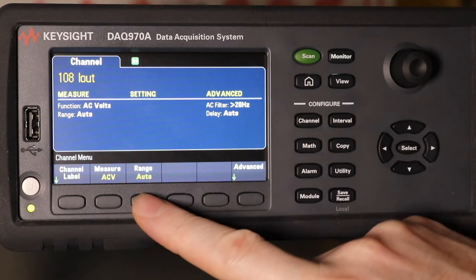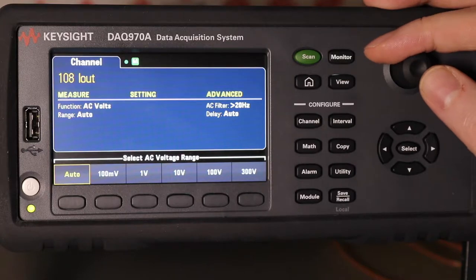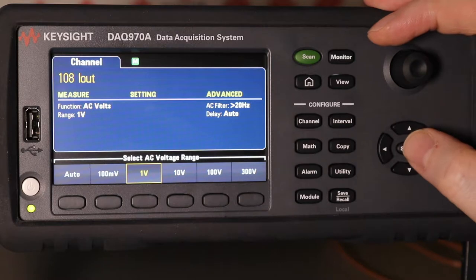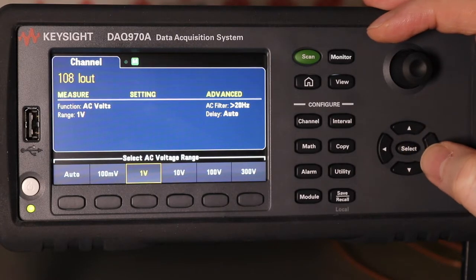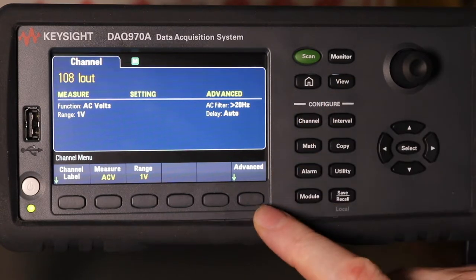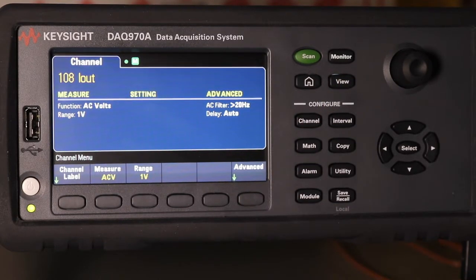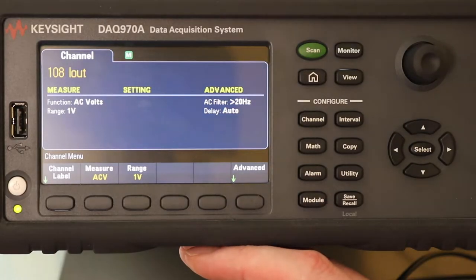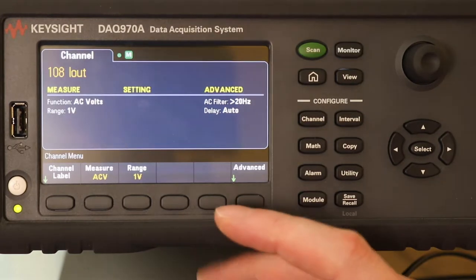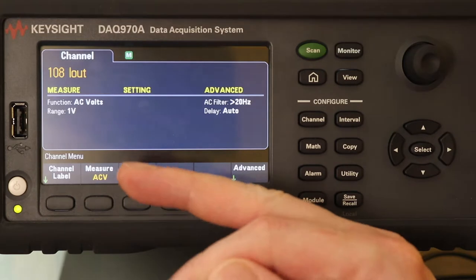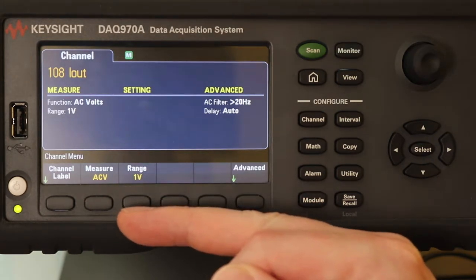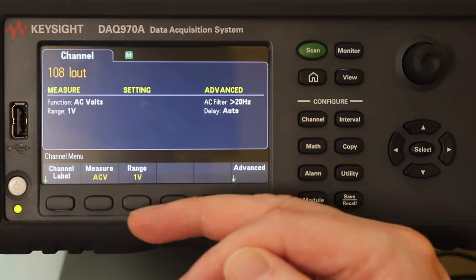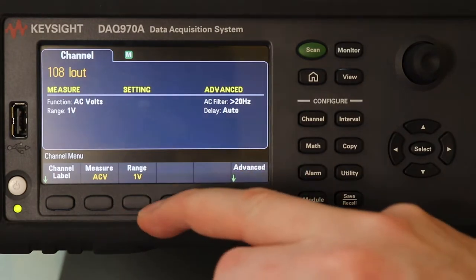It's going to be ACV again. That's 1V max I'll get out of it. You could obviously leave the channels to auto if you wanted. So once we've set the clamp meter up to read on channel 108, it's going to measure volts. My ratio is 5A equals 500mV, so I've set it to 1V range.